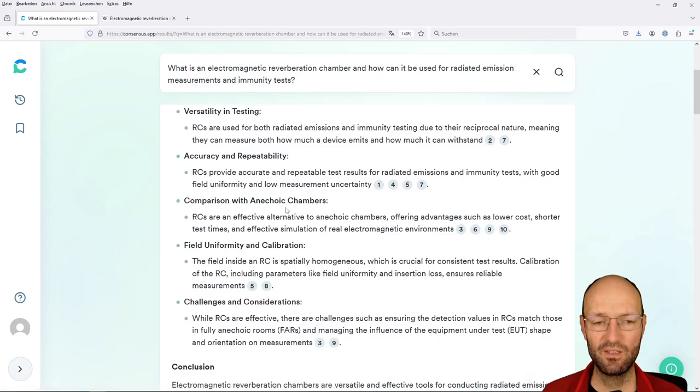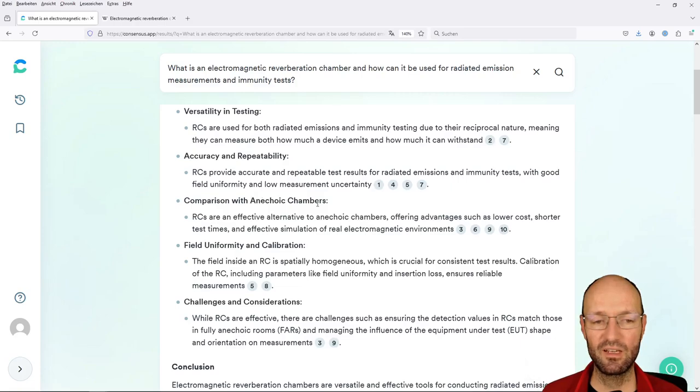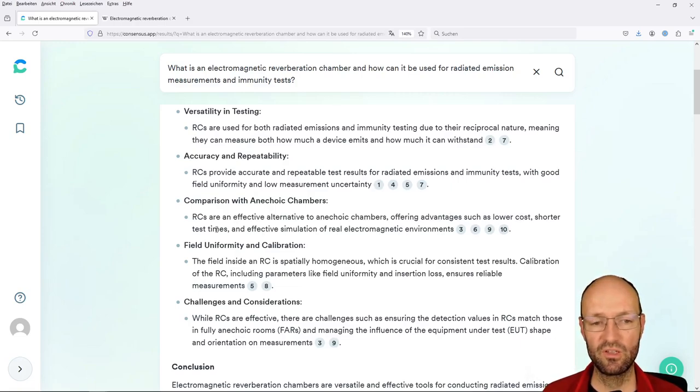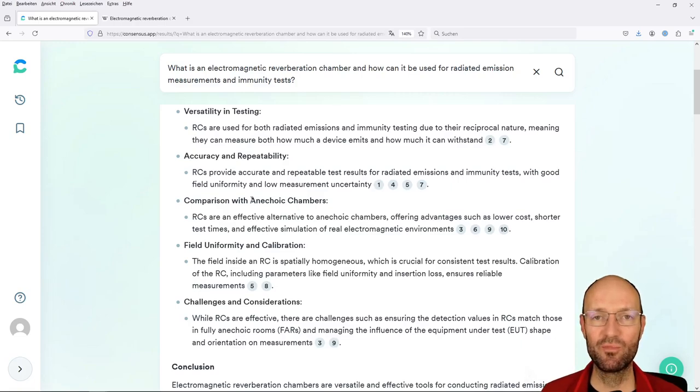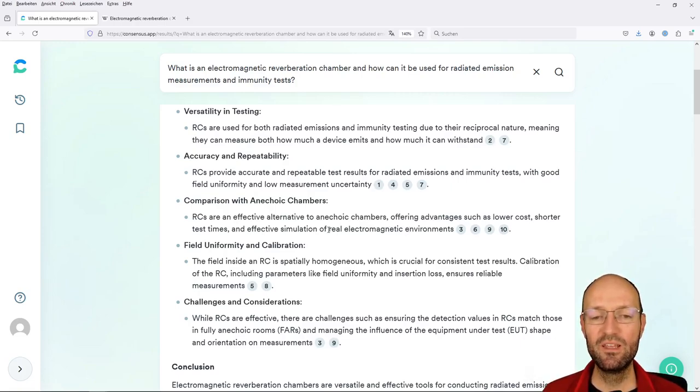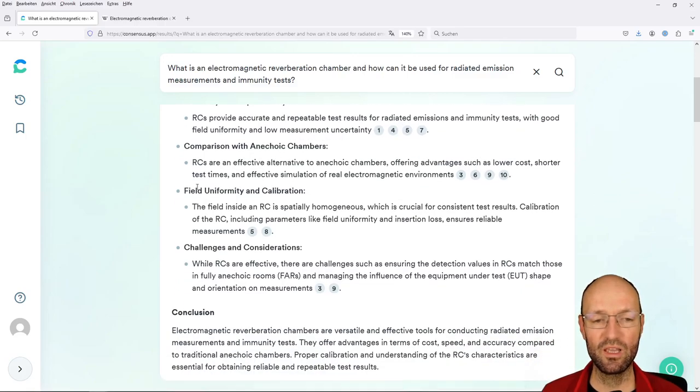So key insights: it's versatile in testing, radiated emission and immunity, reciprocity nature. I think this is good. Accuracy and repeatability we have discussed this. Then the more traditional, the more established test environment for doing these types of tests are anechoic chambers. So here, reverb chambers are advertised as an effective alternative. I would agree offering advantages such as lower costs. I would agree shorter test times. This depends. I would say effective simulation of real electromagnetic environments, more or less.